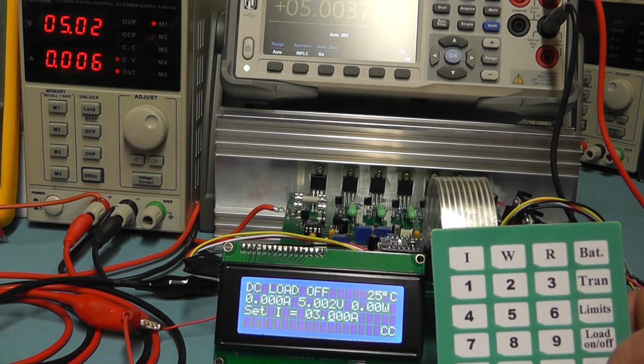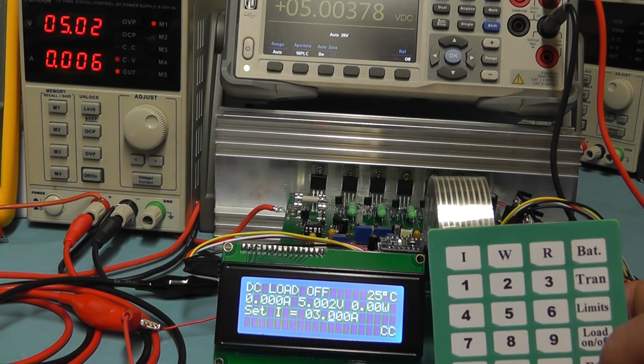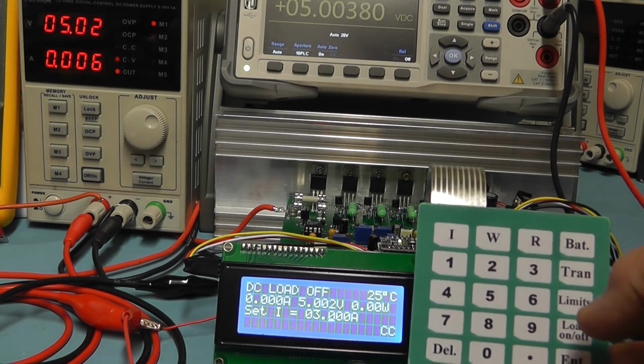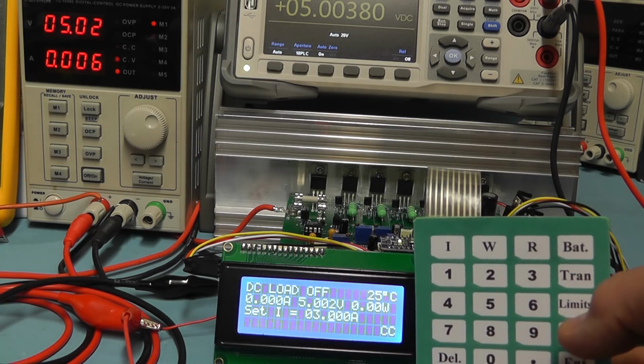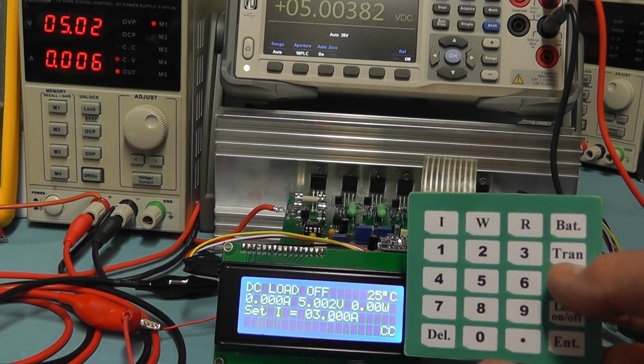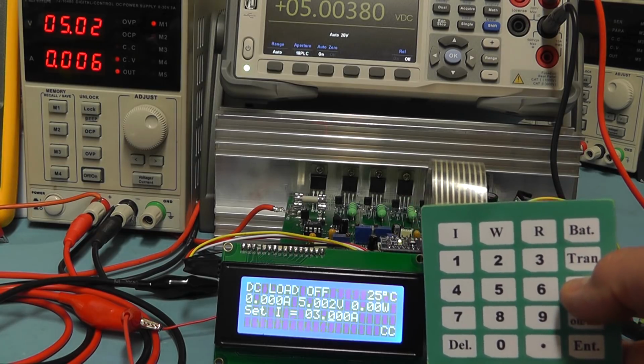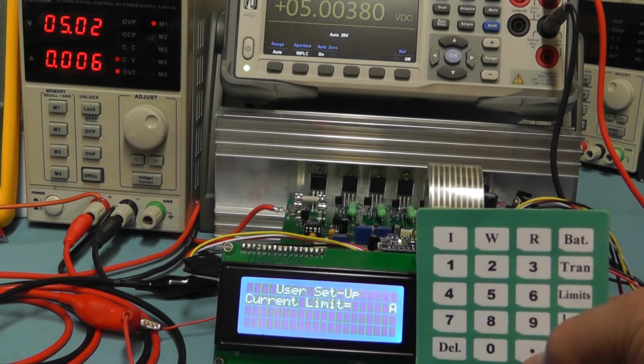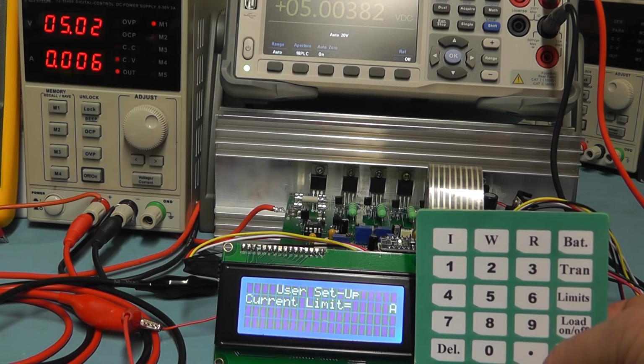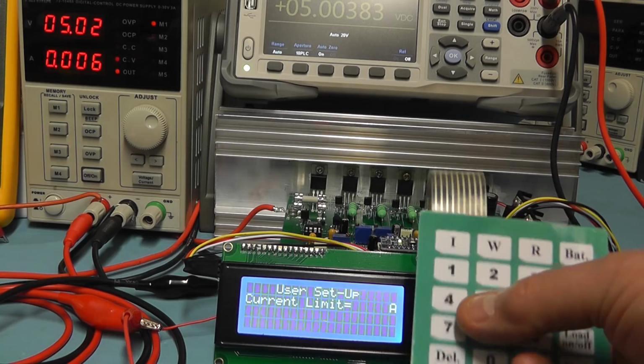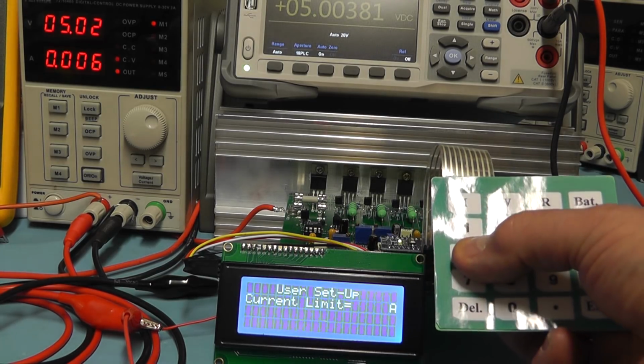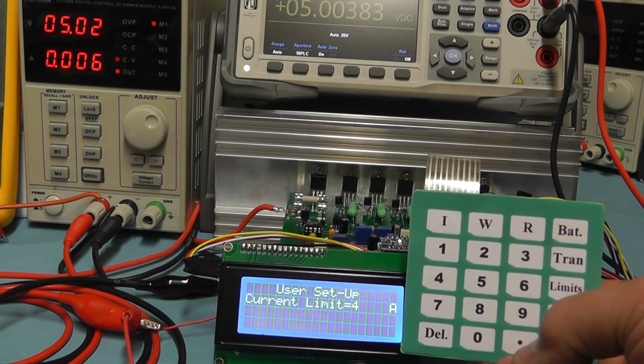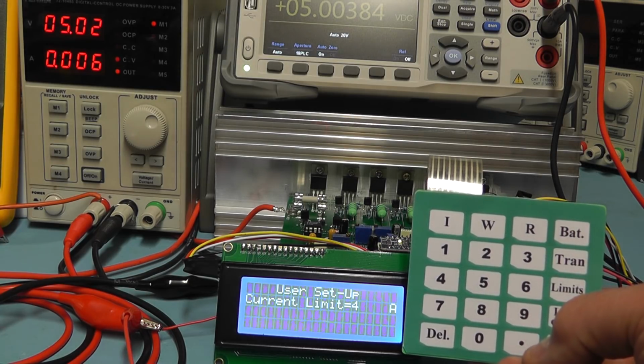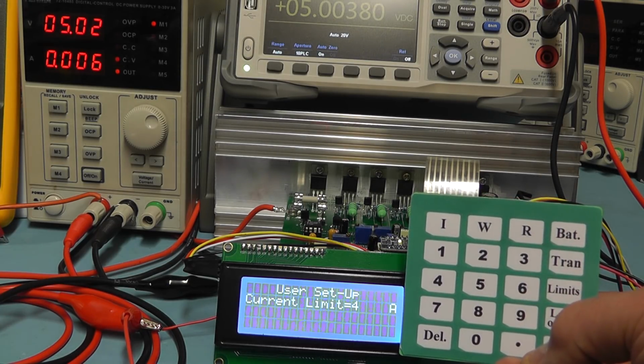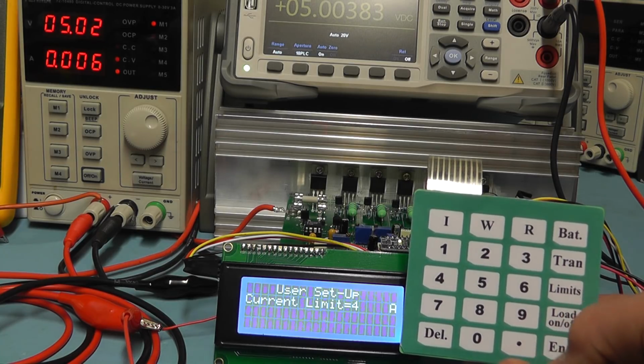I'll now just demonstrate some of the new features we've added to the DC load. And the first one is the user setup limits. So if I press the limits button on the keypad there, it goes to user setup, and the first thing it allows you to do is set the maximum current. So let's say we set that to 4 amps. So we type in 4. This only takes whole numbers for these settings, so you can't do decimal places. So you set it to 4 amps in this case.